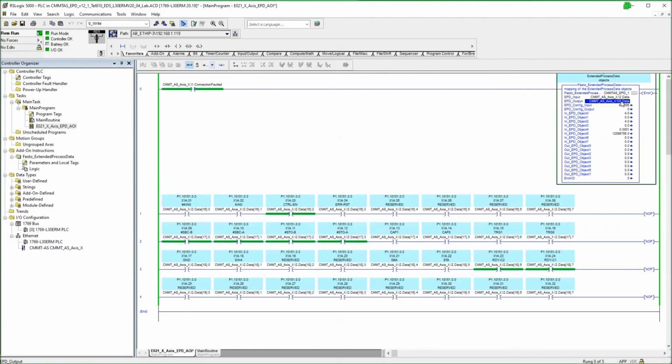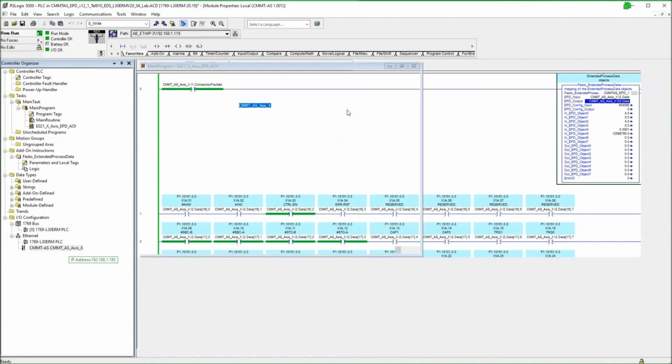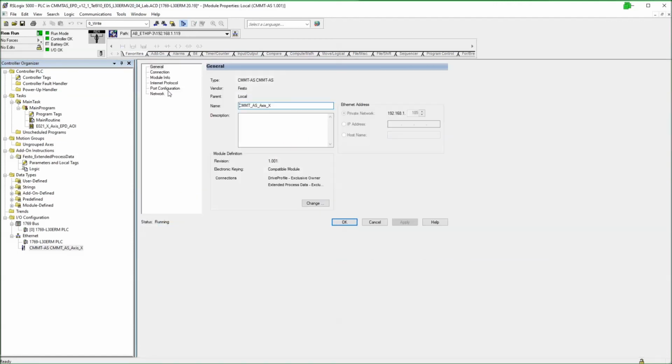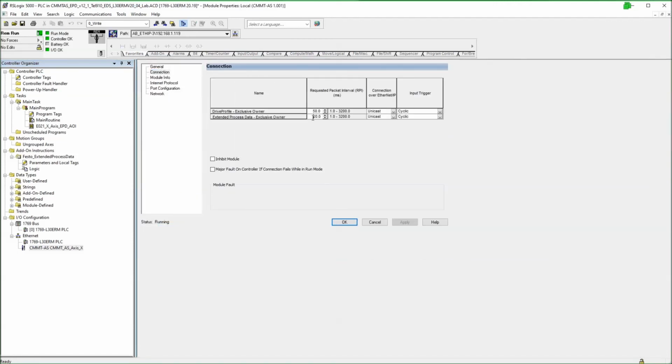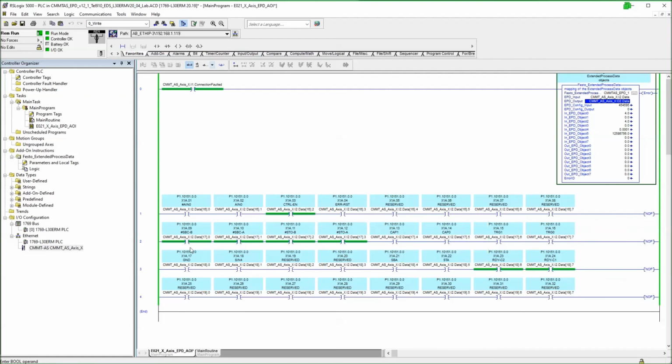And basically the process data is occurring every 20 milliseconds because of the connection that we've associated with already before. Let's quickly show you this again. So the connection, we set it up for 20 millisecond cyclical communications. So that data is coming in every 20 milliseconds.